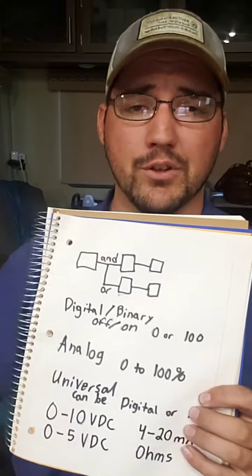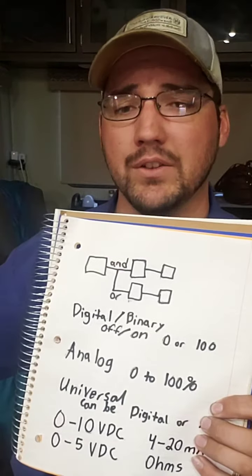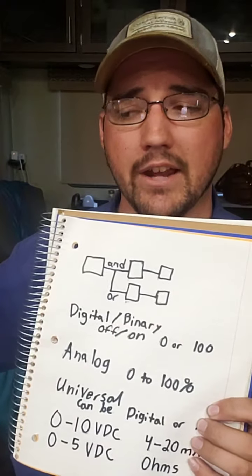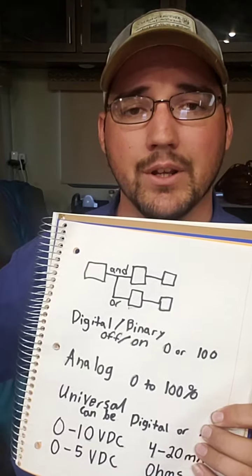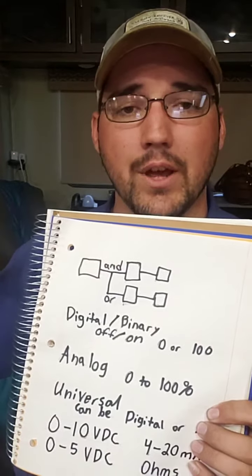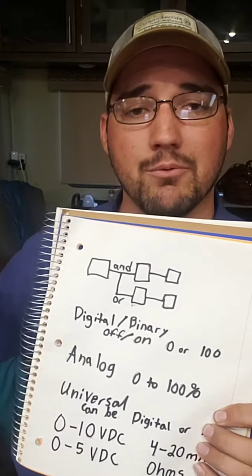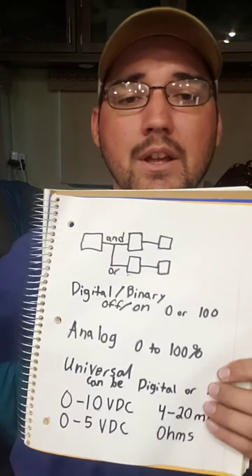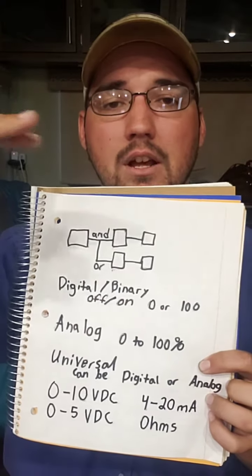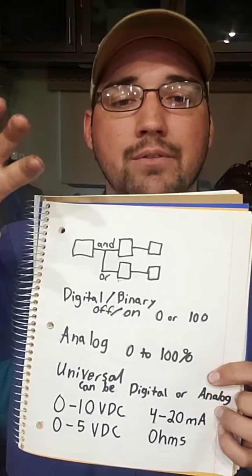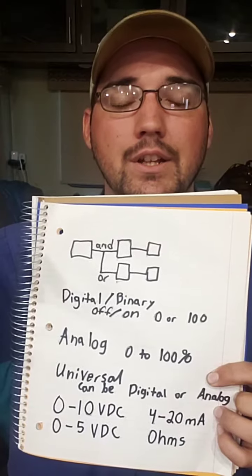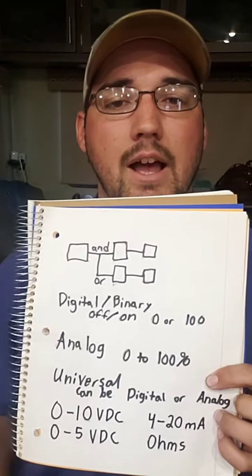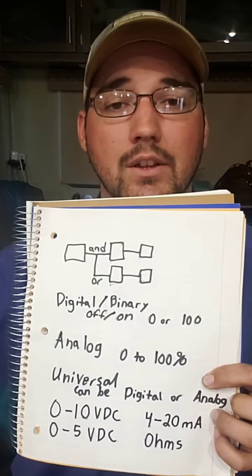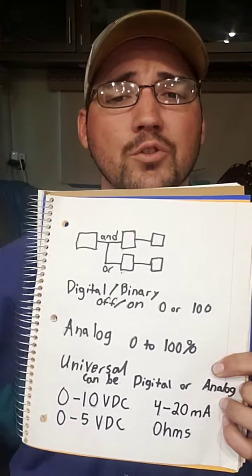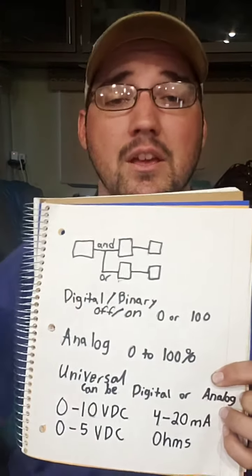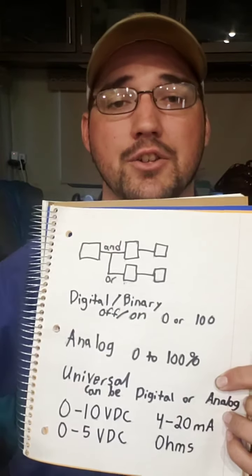Anyway, what they were doing for this VFD to control the tower fan was that the thermistor actually had a little processor board connected to it that converted the temperature itself into a 0 to 10 volt DC signal. We would then run that 0 to 10 volts DC from the sensor to the drive, and I had to program into the drive that when it sees this voltage DC at this input, that means my temperature is X inside my condenser water loop. So those are examples of some inputs and outputs, and yes, VFDs have DDC logic and technology built into them.